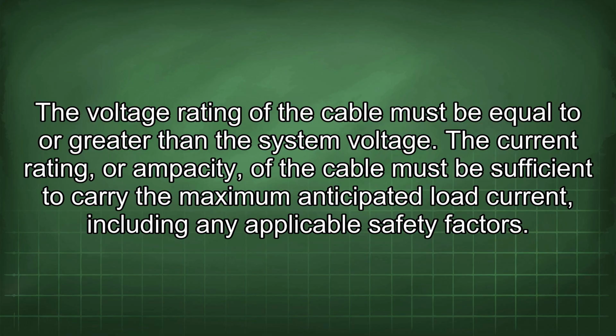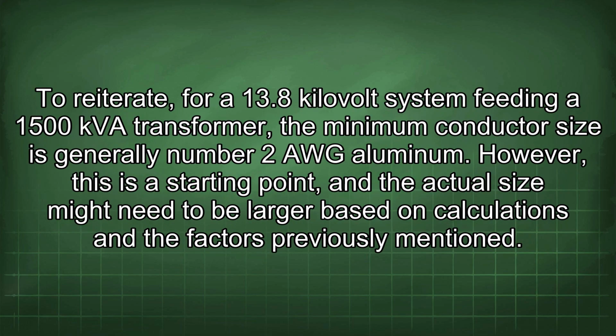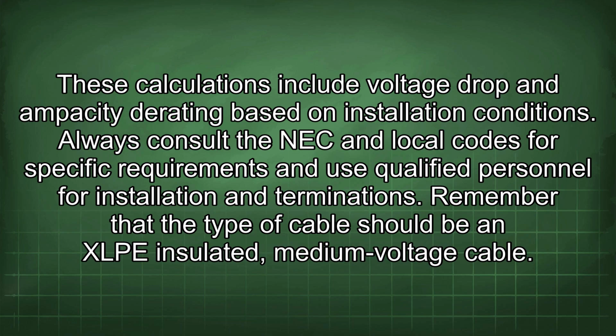To reiterate, for a 13.8 kV system feeding a 1500 kVA transformer, the minimum conductor size is generally number 2 AWG aluminum. However, this is a starting point, and the actual size might need to be larger based on calculations and the factors previously mentioned. These calculations include voltage drop and ampacity derating based on installation conditions. Always consult the NEC and local codes for specific requirements and use qualified personnel for installation and terminations.